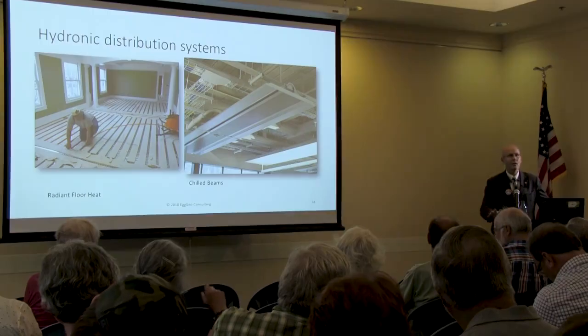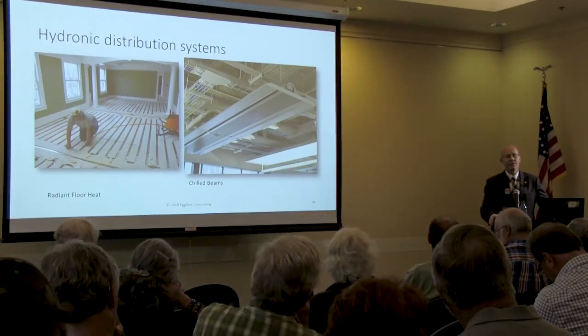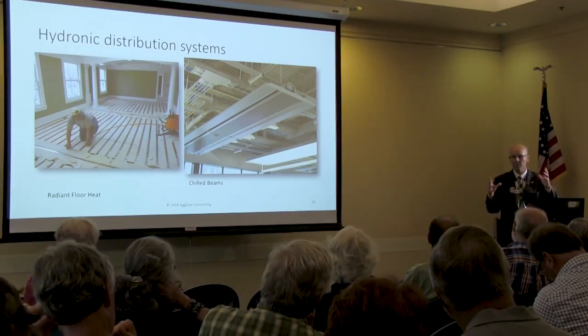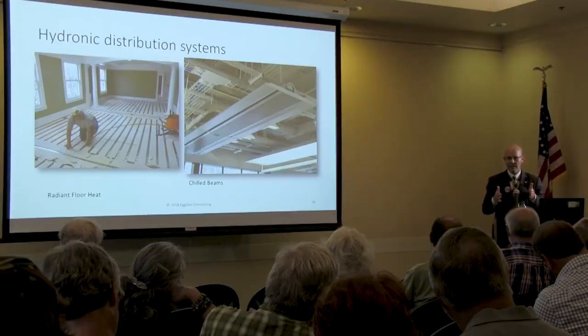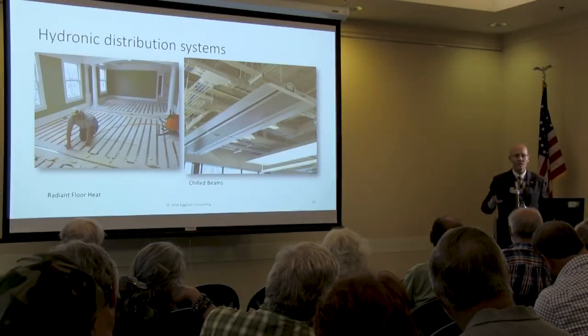When I say so simple, I don't want to oversimplify it. If the campus that we're talking about has a distributed steam pipe system, that's a lot warmer than distributed hot water. But here's the trick, and this is where you have to get into the weeds. That steam is going through exchangers at the individual buildings, and it's exchanging with a condenser water loop, a heated water loop that's actually delivering water between 170 and 190 degrees probably. And if you can't deliver that, well, let me just say this.